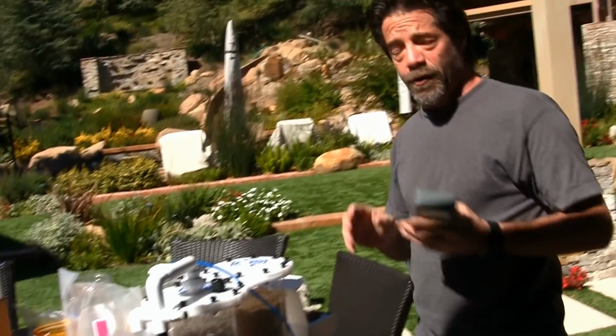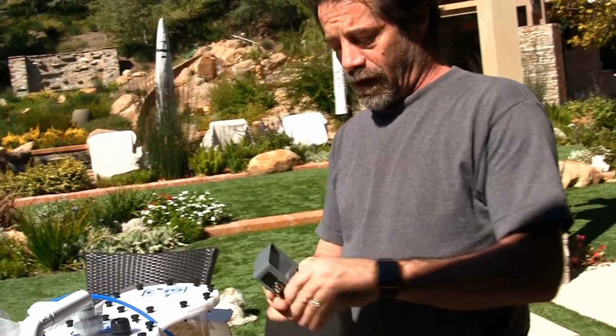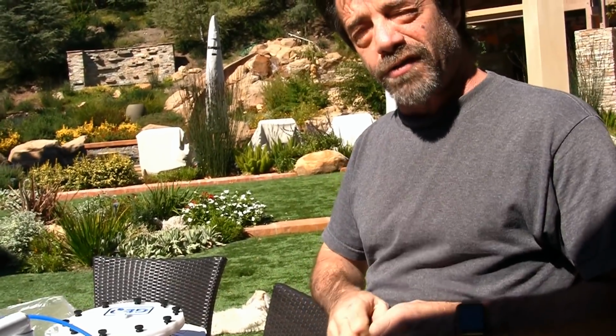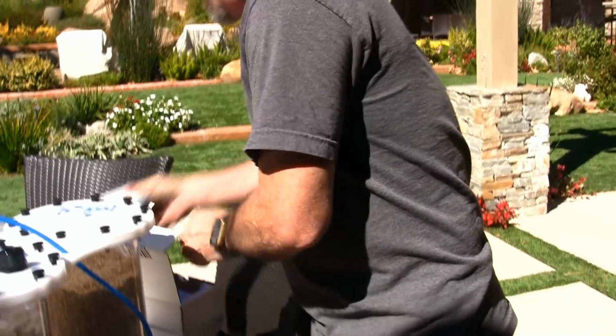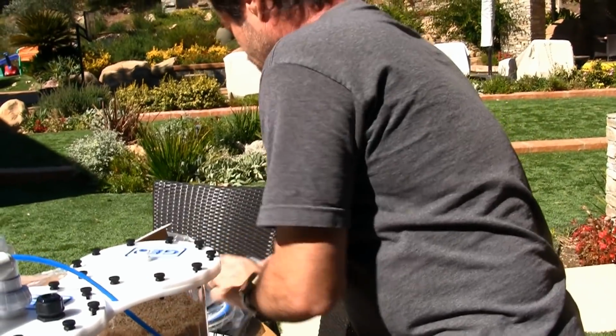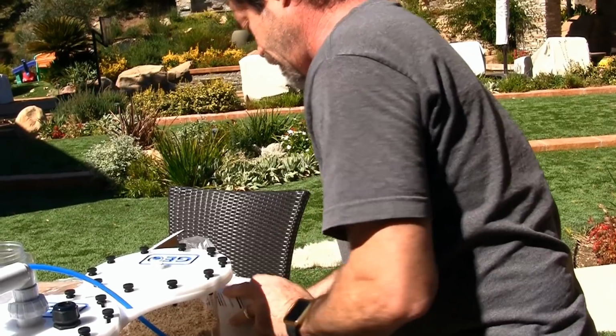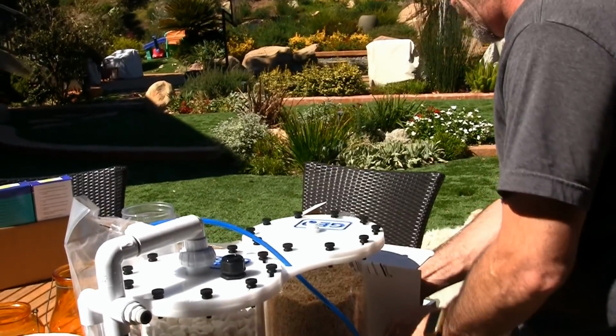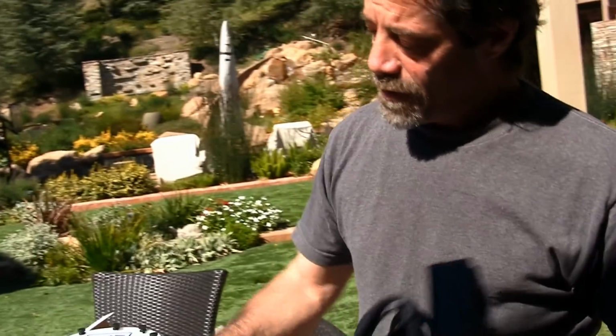So we're going to need to monitor pH inside the reactor. This is a PM2 module, which will give us an additional pH probe in the system. That pH probe will go in the top of the calcium reactor and it will monitor the pH inside the reactor.